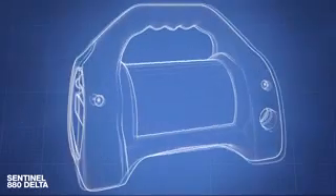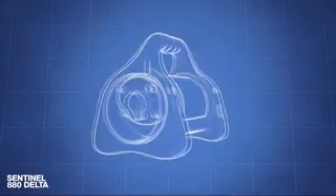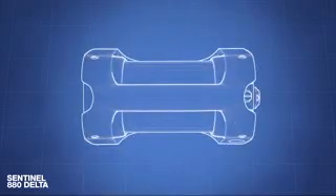Model 880 projectors are primarily used for the industrial application of gamma radiography using Iridium-192 to inspect materials and structures within the density range of approximately 2.71 grams per cubic centimeter through 8.53 grams per cubic centimeter.